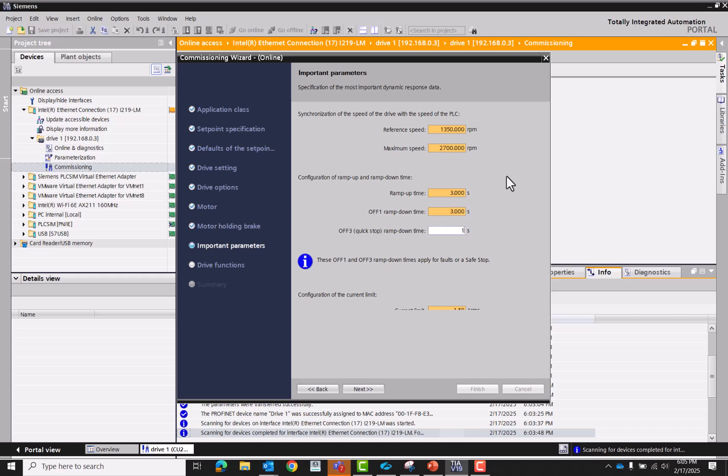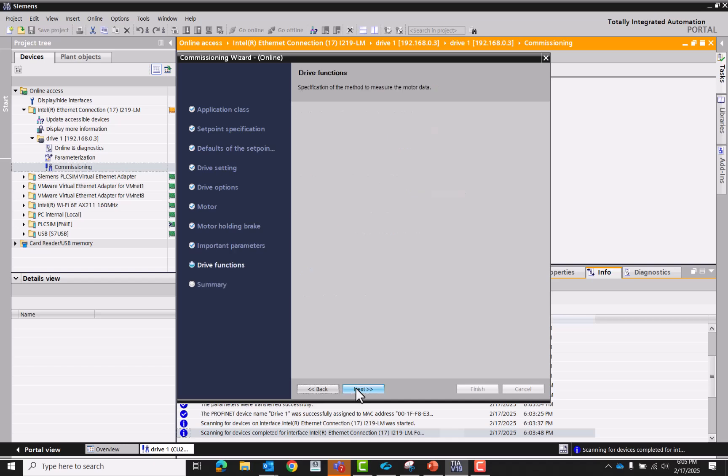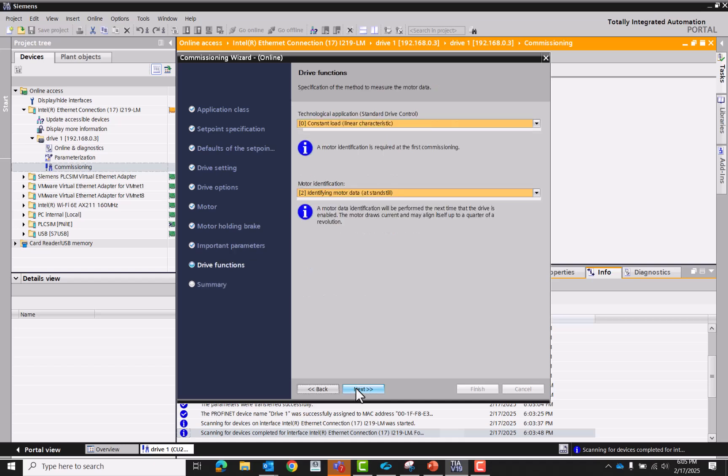And then one second quick off. For some reason this scaling on my PC is off a little bit, but that's the current limit and it's set at 150. We're gonna do motor optimization, so an auto tune, I'm gonna do that at standstill.